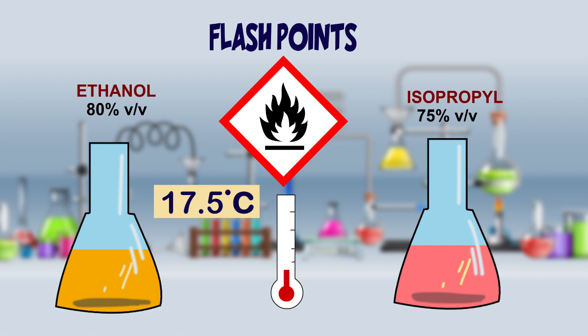The flash point of ethanol 80% volume by volume and of isopropyl alcohol 75% volume by volume is 17.5 degrees Celsius and 19 degrees Celsius respectively. National safety guidelines and local legal requirements must be adhered to for the storage of ingredients and the final product.